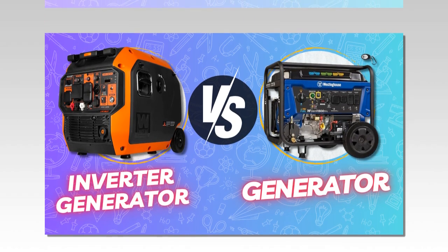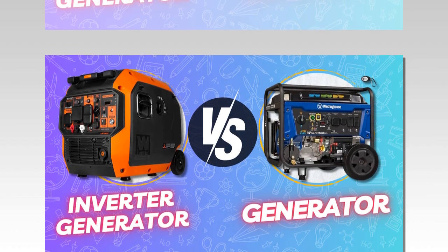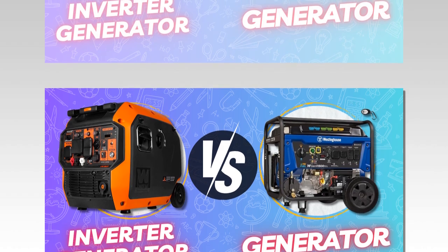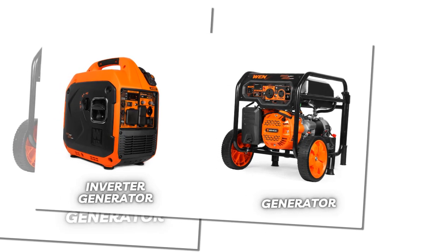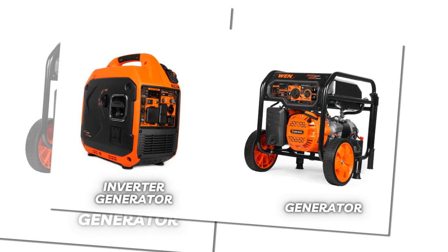Now, the inverter generator is where things get a bit more sophisticated. Okay, I'm intrigued. You said it uses an engine and electronics. How does that change things? It's this really clever three-step process. First, yes, the engine generates AC power, sort of like the traditional one. Okay. But then step two, that AC power immediately gets converted into DC power. Right, like battery power. Kind of, yeah. It's an intermediate step. And then step three, that DC power is converted back into AC using sophisticated inverter electronics. So it converts it twice, AC to DC, then DC back to AC.